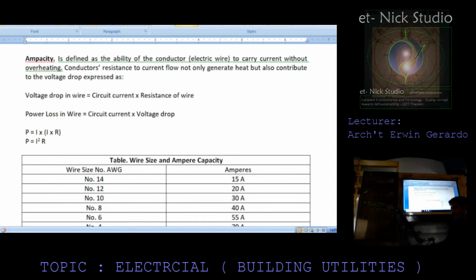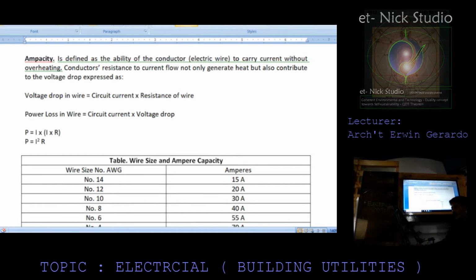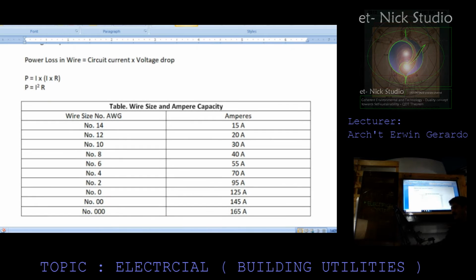current without overheating. A conductor's resistance to current not only generates heat but also contributes to the voltage drop. Voltage drop in wire is equal to the circuit current times the resistance of the wire. Power loss in wire is equal to the circuit current multiplied by the voltage drop. Therefore, power is equivalent to I times resistance, and therefore P equals I raised to the second power times resistance.